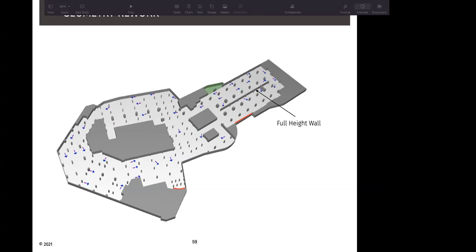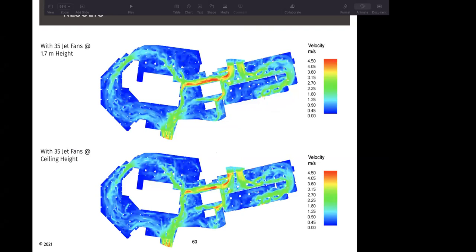So what was considered was a full height wall. What it would do is force the air to go around the wall rather than across it. So instead of letting it take the shortest route, we are forcing it to take a longer route around the full height wall. If we look at the visibility contours, the air is forced around the full height wall to now access the exhaust shaft across it.